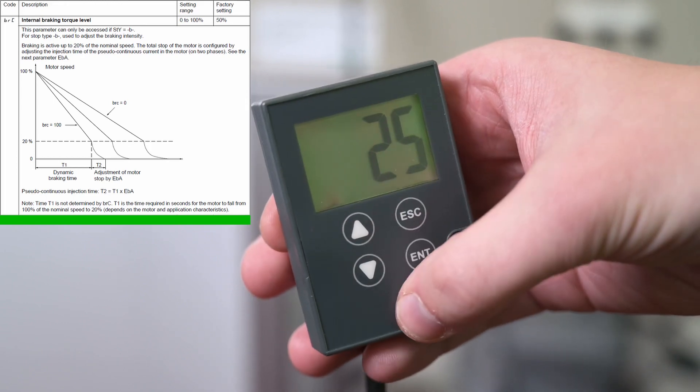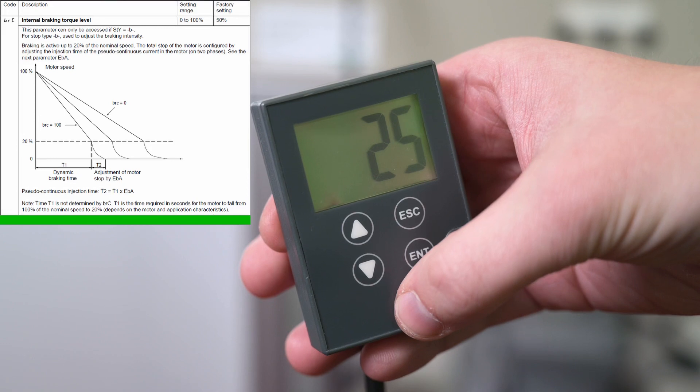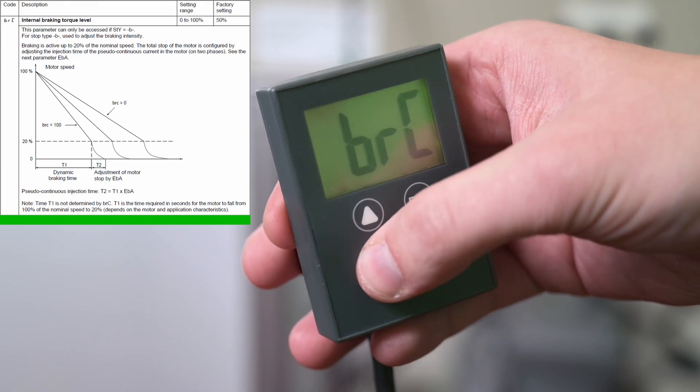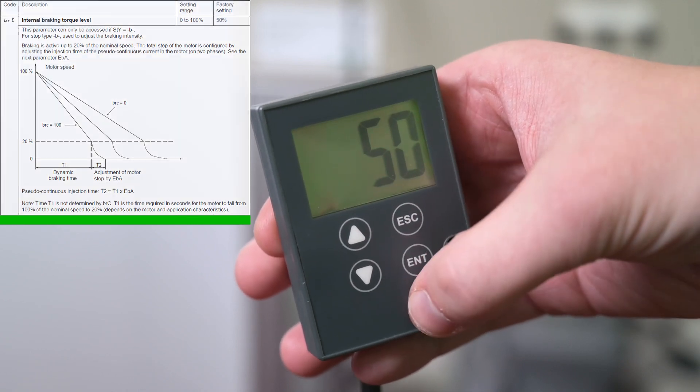First, we configure the parameter BRC, which defines until when the soft braking is active. The value is a percentage of the nominal speed. Now we configure EBA. This parameter allows us to adjust the current injection time. It will stop the motor. Here, you can see the motor slowing down at first and quickly stopping at the end.